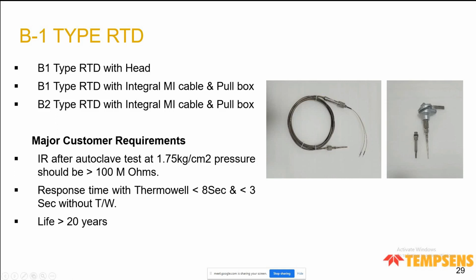And the second important thing the customer needs is that the response time of this RTD with the thermowell has to be less than 8 seconds. So for this there is a very special design. The insert is tapered and it is made of silver, and inside the thermowell also a taper drill is there, so that when the RTD is touching the surface of the thermowell there is good contact along the length of the RTD. So that is how it is able to give a less than 8 second response time with the thermowell, and without the thermowell it is less than 3 seconds.